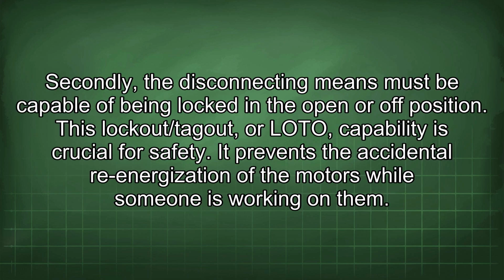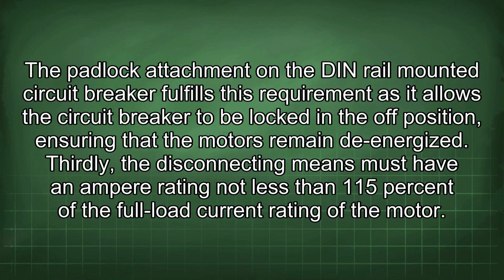Secondly, the disconnecting means must be capable of being locked in the open or off position. This lockout/tagout, or LOTO, capability is crucial for safety. It prevents the accidental re-energization of the motors while someone is working on them. The padlock attachment on the DIN rail-mounted circuit breaker fulfills this requirement as it allows the circuit breaker to be locked in the off position, ensuring that the motors remain de-energized.